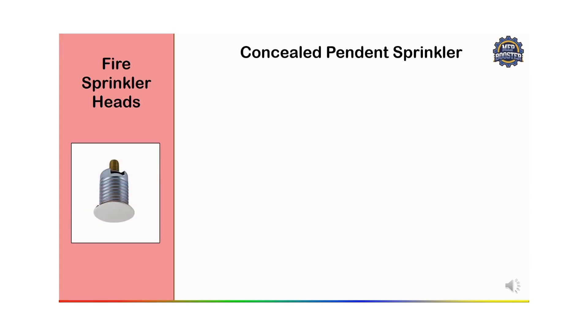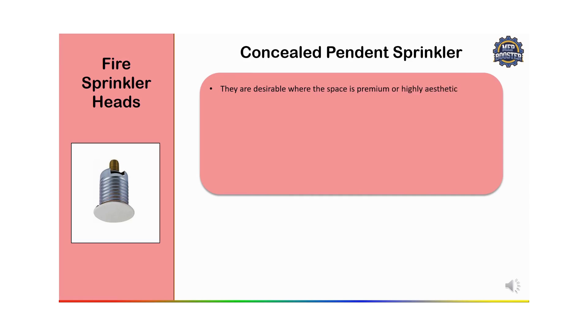The next type is the concealed pendant sprinkler. Concealed sprinklers are installed within a cover plate or ceiling tiles and remain hidden until activated. The cover plate falls away when the sprinkler head is activated. They are desirable where the space is premium or highly aesthetic. Concealed pendant heads are recessed into the ceiling, mounted with a decorative cover that blends with the ceiling, and maintain a clean ceiling line, hiding the sprinkler head until needed. This type is suitable for aesthetically sensitive environments.